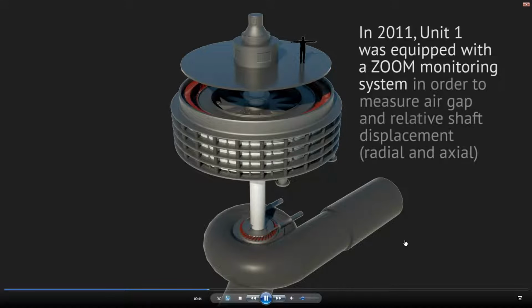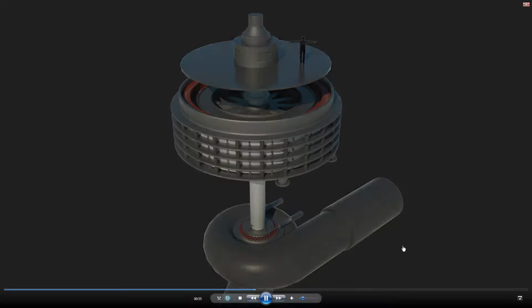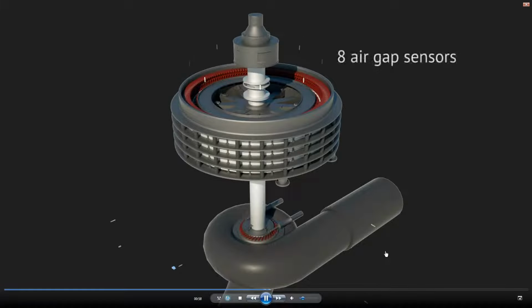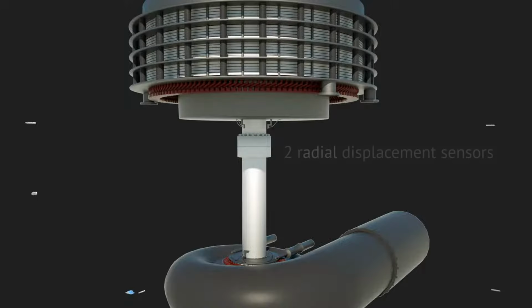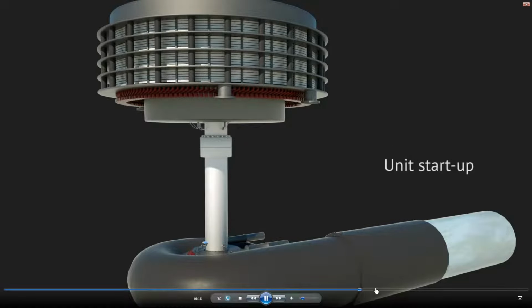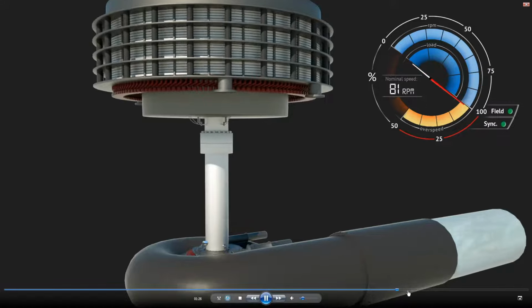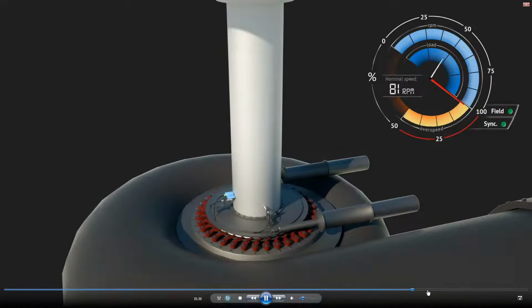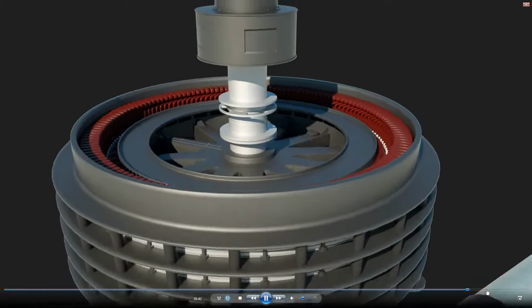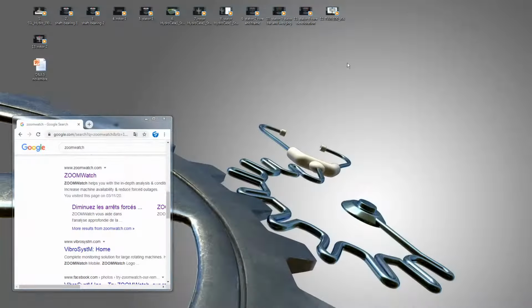So this unit had a system installed in 2011, equipped with a Zoom system that included measuring air gap, relative shaft displacement, radial and axial. We can see that 8 air gap sensors were installed at the upper part of the unit. They had radial displacement probes at the lower guide bearing and 2 more at the turbine guide bearing, and they had an axial probe as well, and our famous synchronization probe. We did all kinds of testing, including a startup and a field flash, and I wanted to show you the results that we were able to observe.